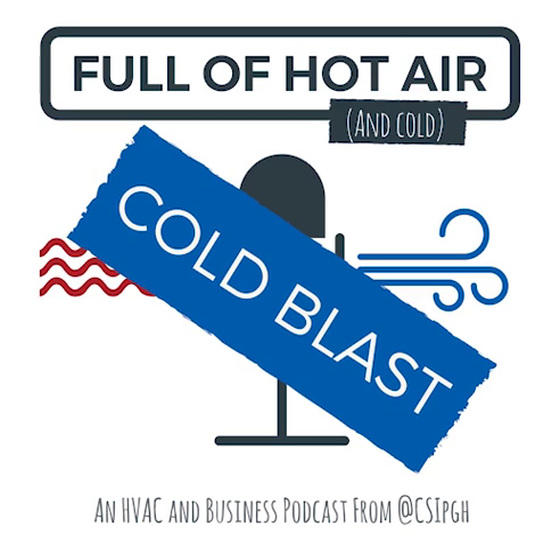A lot of the other part of it is just listening to a blower in a system. A lot of seasoned techs can tell if it's working hard, how noisy it is, how quiet it is. But let's say we want to know what the CFM is going through this system right now, and we want to use the resources we have. Let's start with a furnace. With a furnace, we already know the BTUs because it's going to be on the data plate. Knowing that, we can use it as a source to find out what our airflow is.